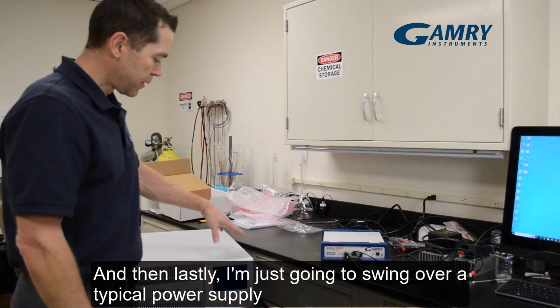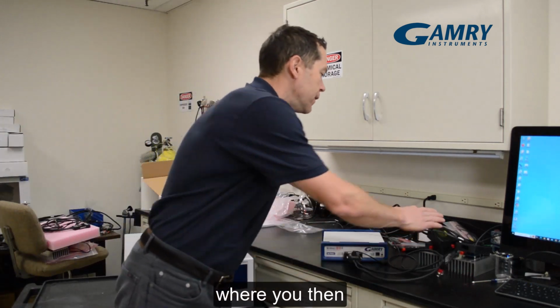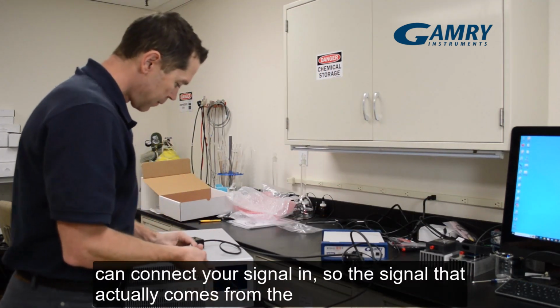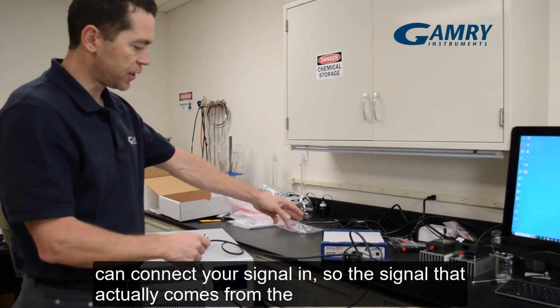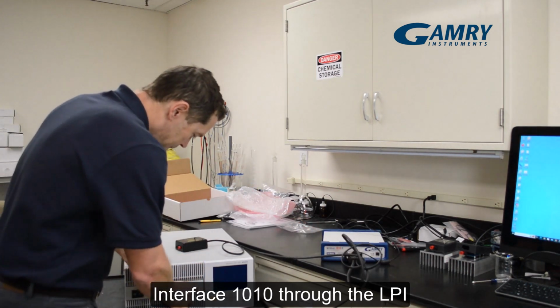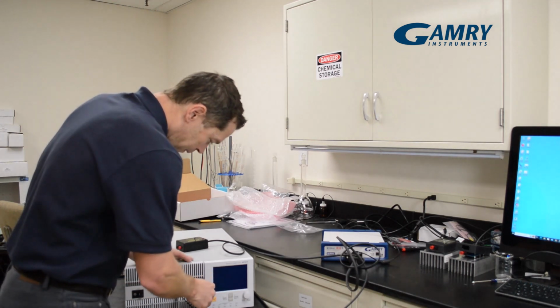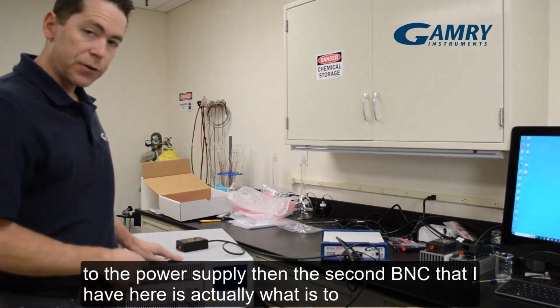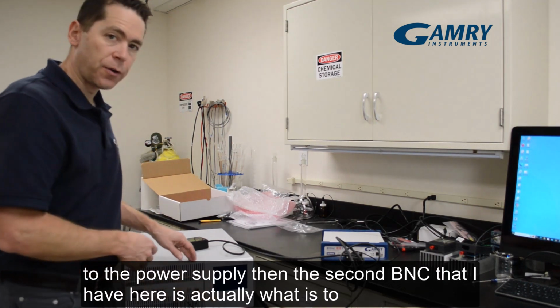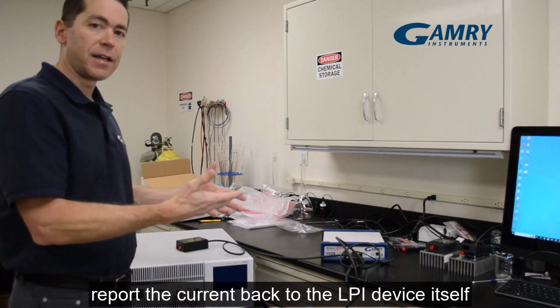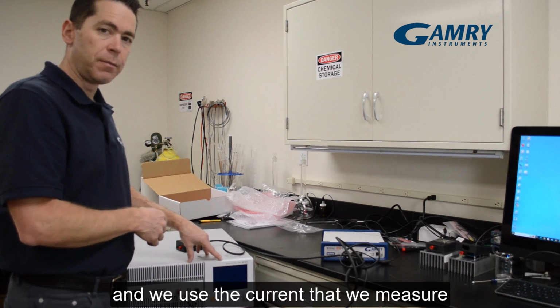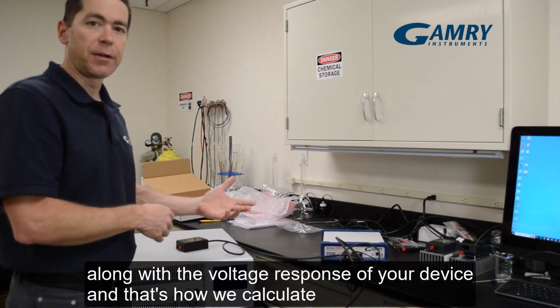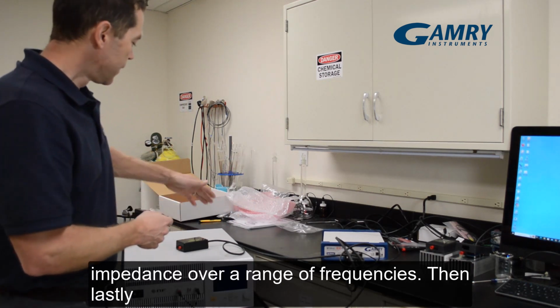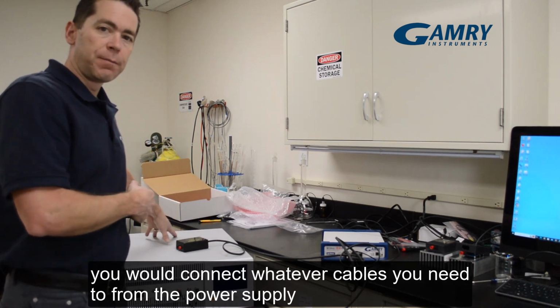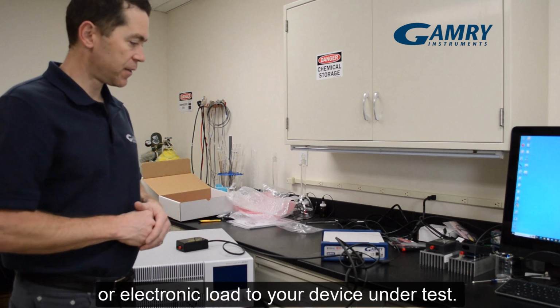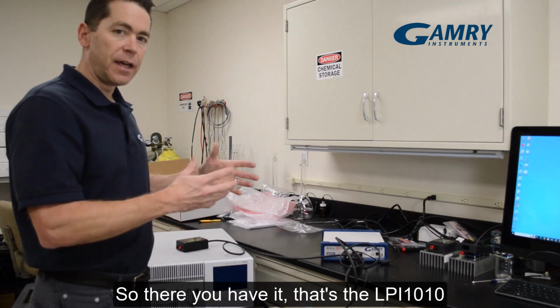And then lastly, I'm just going to swing over a typical power supply where you then can connect your signal in, so the signal that actually comes from the interface through the LPI, to the power supply. Then the second BNC that I have here is actually what's going to report the current back to the LPI device itself, and that's how we use the current that we measure along with the voltage response of your device, and that's how we calculate the impedance, obviously over a range of frequencies. Then lastly, you would connect whatever cables you need from the power supply or the electronic load to your device under test. So there you have it. That's the LPI1010 and what's contained within the box.